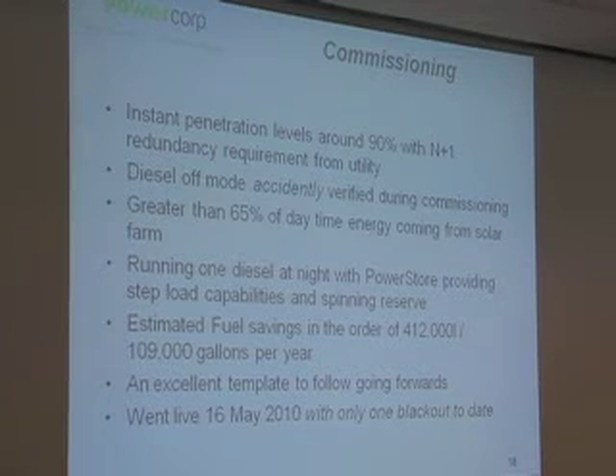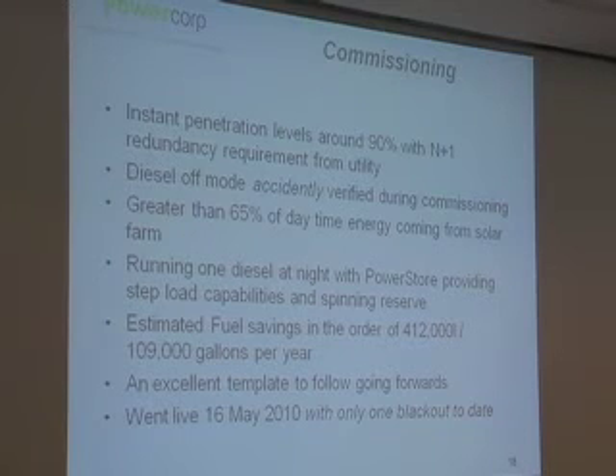So we're seeing greater than 65% of the daytime energy coming from the solar. I've touched on running one diesel at night, and the estimated fuel savings based on what we've seen to date after going live in May last year is about 412,000 litres, or about 100,000 gallons. And if you're paying anywhere from $6 to $8 a gallon, it starts to add up pretty quickly.